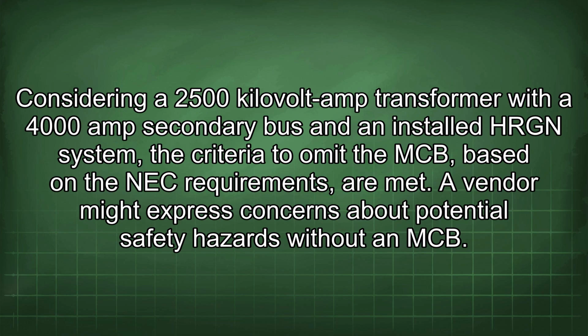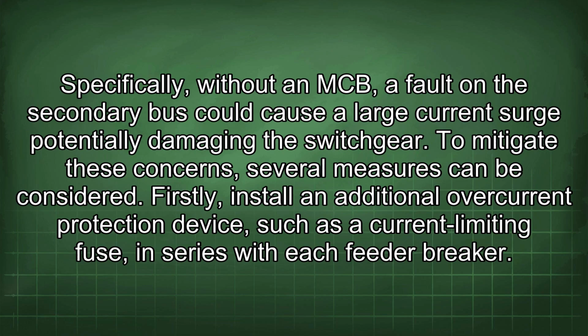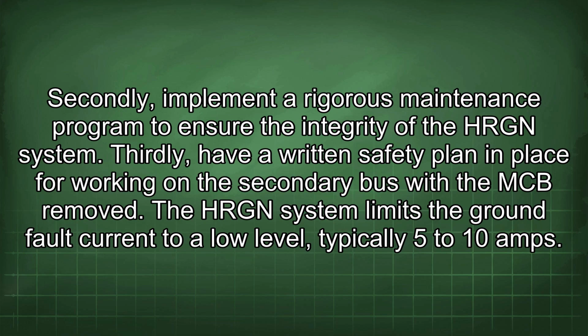A vendor might express concerns about potential safety hazards without an MCB. Specifically, without an MCB, a fault on the secondary bus could cause a large current surge, potentially damaging the switchgear. To mitigate these concerns, several measures can be considered. Firstly, install an additional overcurrent protection device such as a current limiting fuse in series with each feeder breaker. Secondly, implement a rigorous maintenance program to ensure the integrity of the HRGN system. Thirdly, have a written safety plan in place for working on the secondary bus with the MCB removed.